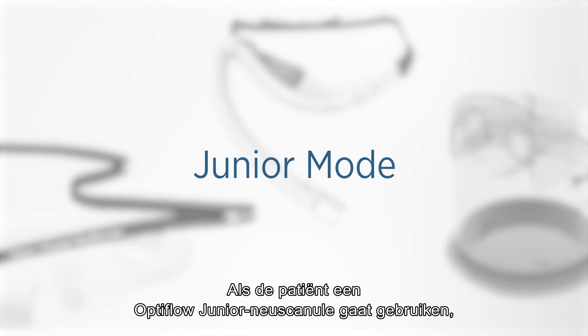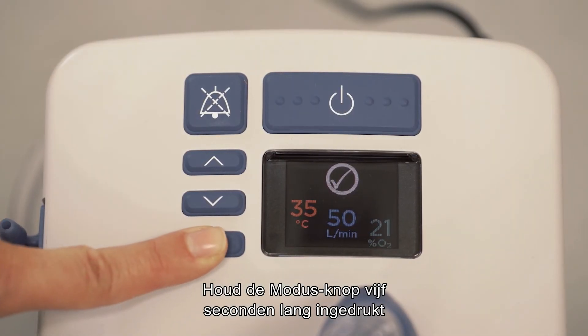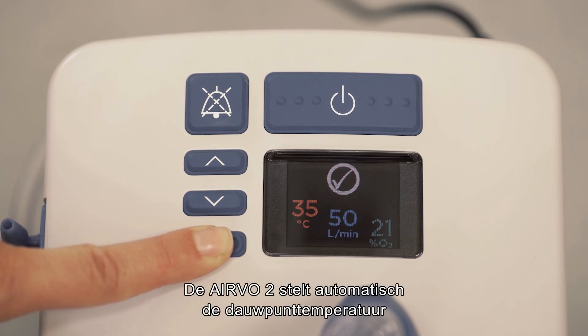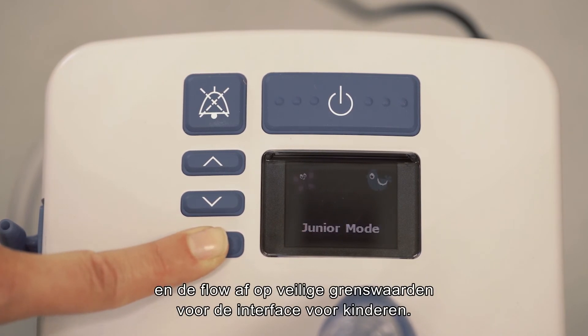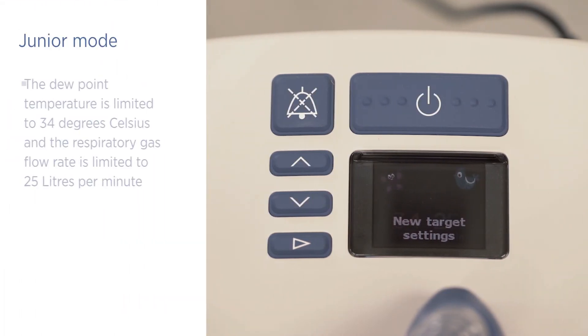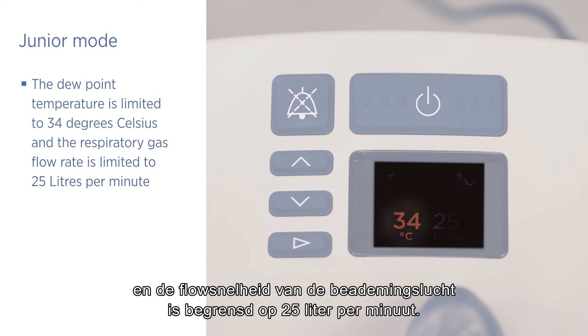If the patient will be using an OptiFlow Junior nasal cannula, you must activate junior mode. Press and hold the mode button for five seconds until the junior mode symbol appears. The AIRVO 2 will automatically adjust the dew point temperature and gas flow to safe limits for the junior interface: the dew point temperature is limited to 34 degrees Celsius and the respiratory gas flow rate is limited to 25 litres per minute.